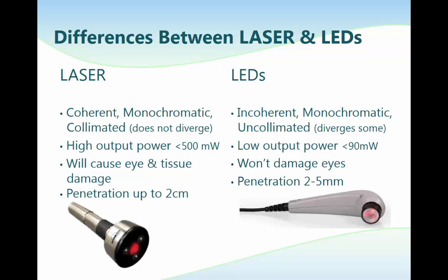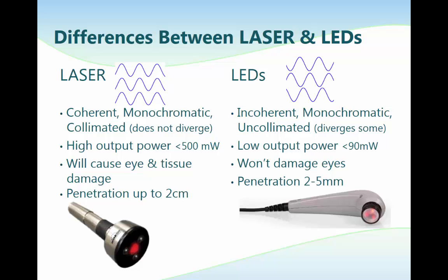It is important to examine the differences between laser and LED. For light therapy to be classified as laser, it must be coherent, monochromatic, and collimated. Lasers have a high output power at or below 500 milliwatts and have the potential to cause eye and tissue damage, with a depth of penetration of approximately 2 centimeters. LEDs are incoherent, monochromatic, and uncollimated. They have a low output power of less than 90 milliwatts, will not damage eyes, and have a depth of penetration of approximately 2 to 5 millimeters.